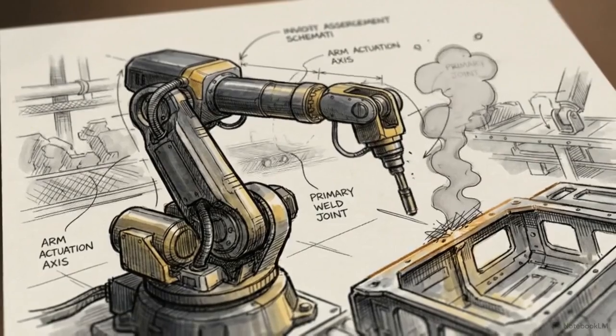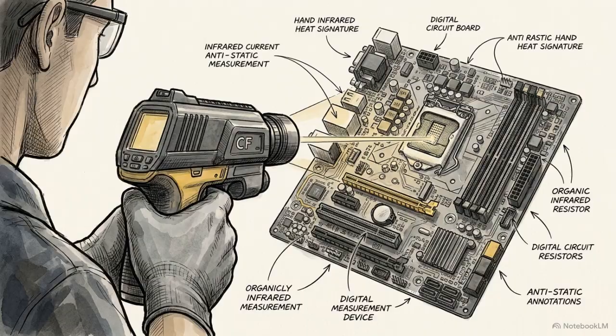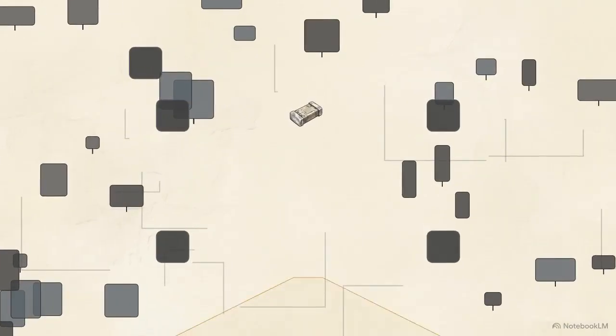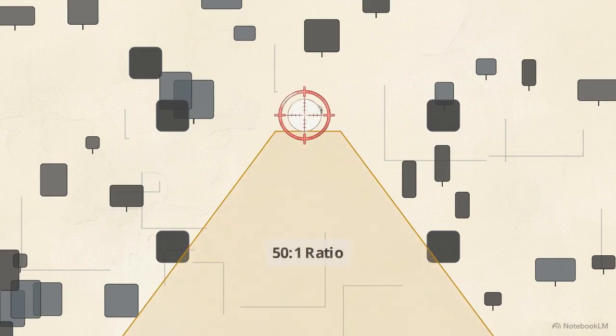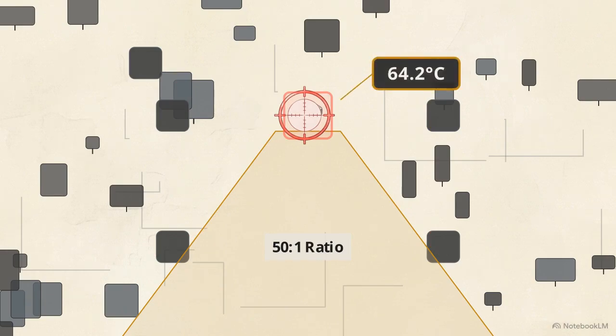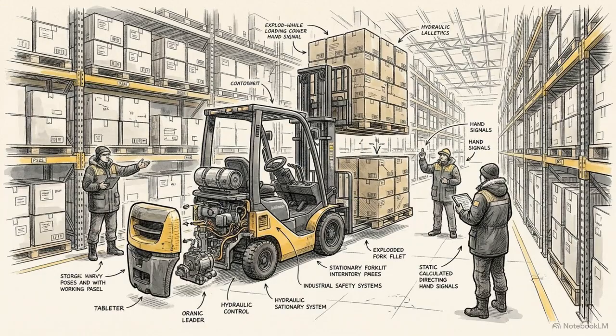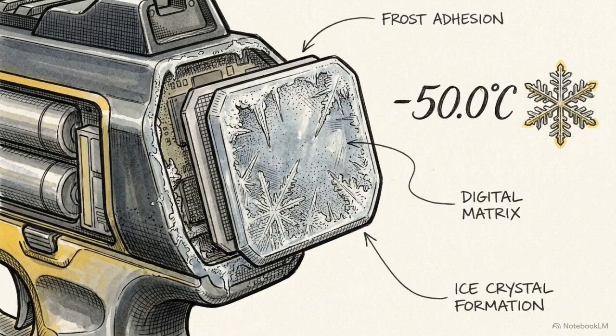Different environments demand highly specific focal behaviors. For electrical benchwork, engineers utilize the close focus, or CF model. It employs a tighter 50-to-1 distance ratio, allowing a technician to isolate the exact temperature of a microscopic 6mm resistor on a dense circuit board without pulling in ambient heat from adjacent components. Conversely, the Sub-Zero variant was engineered strictly for the logistics of the global cold chain. Its sensors are recalibrated for extreme accuracy in commercial walk-in freezers down to -50°C.